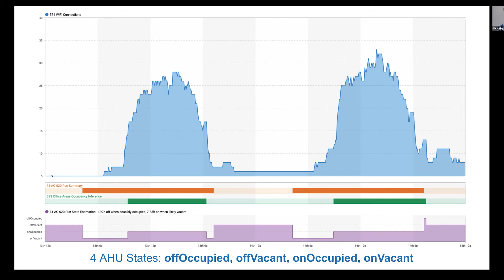So we came up with a color scheme, converting this to our favorite visualization, the heat map, giving us a 3-dimensional chart. If we're looking at a day's worth of time with 3 different air handlers along this scale, we have off-vacant areas in gray, on-and-vacant periods in orange. Here's an air handler starting up quite a bit earlier than anybody actually arrives. In red we show the worst case, where we've already turned off the HVAC system but believe somebody's still present.